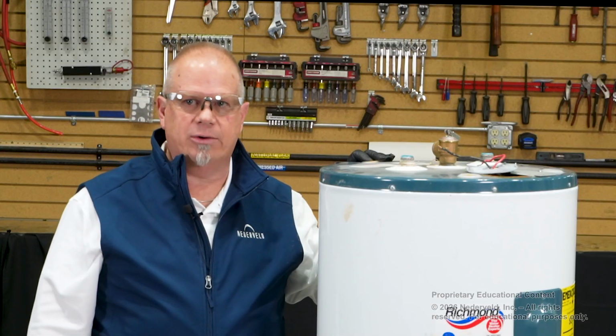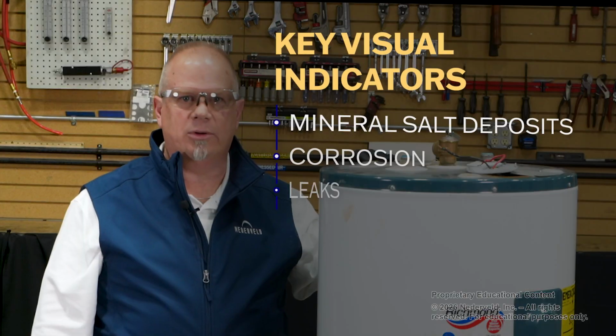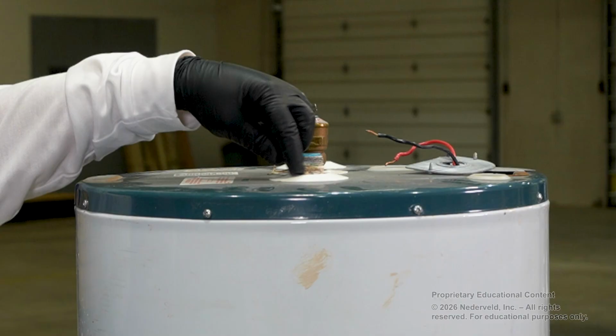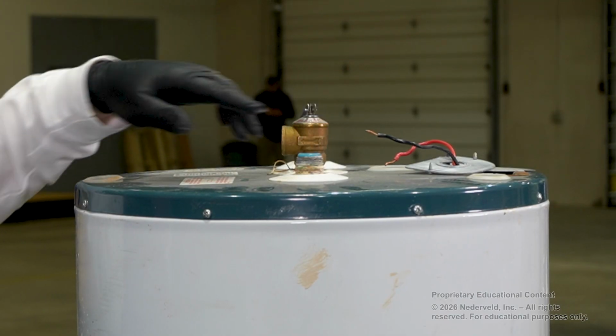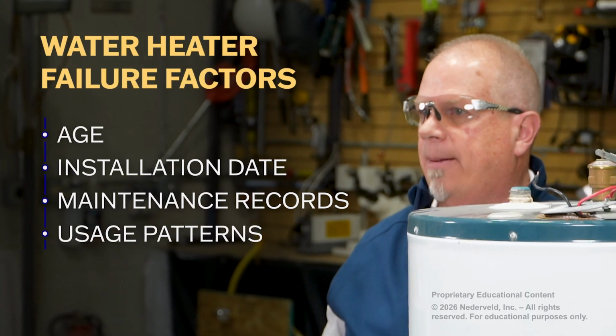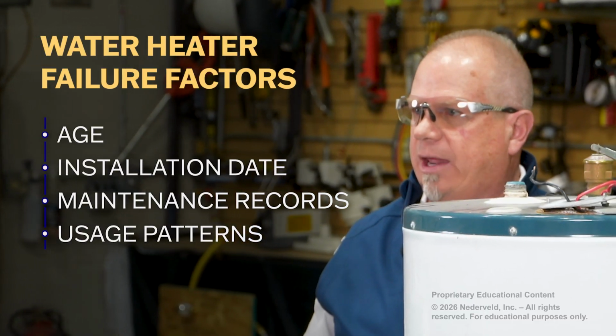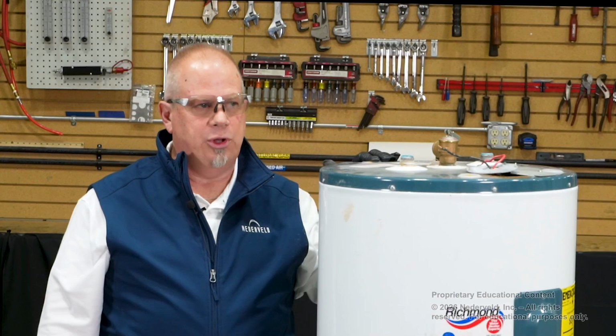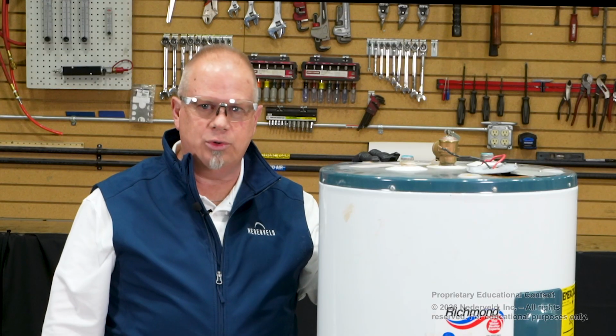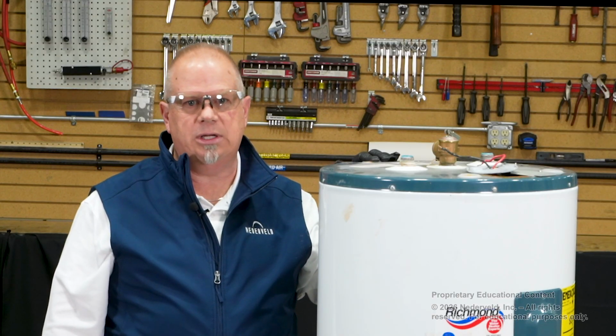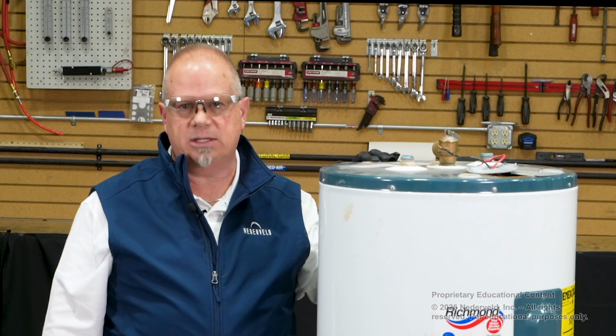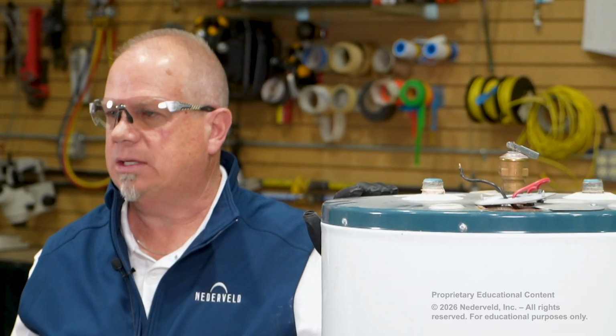Key visual indicators on a water heater include the presence of mineral salt deposits, corrosion, and leaks. In this case, we have mineral salt deposits at the inlet. Age, installation date, maintenance records, and usage patterns are all issues to consider. The use of recirculation pumps or use for hydronic heating are also conditions that can greatly reduce life expectancy of a water heater. Water heaters, in many cases, have a leakage point that is concealed.